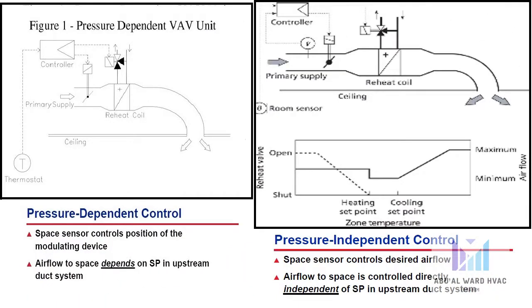A pressure dependent VAV control scheme uses the space temperature sensor to directly control the position of the modulating device. The actual airflow delivered to the space is a byproduct of that position and depends on the duct system static pressure at the inlet of the terminal unit.